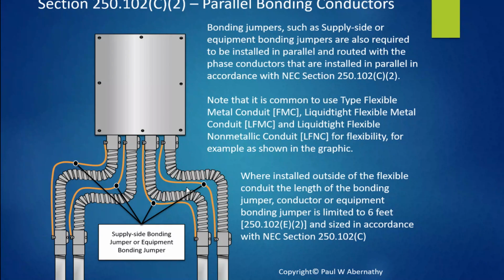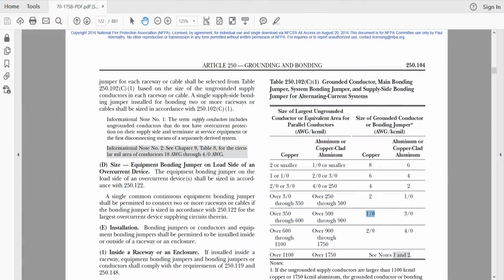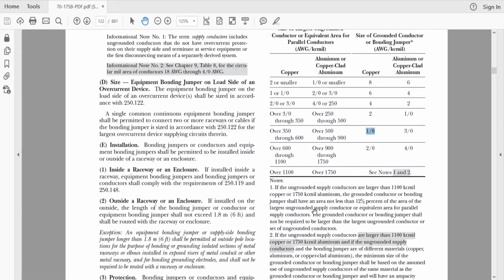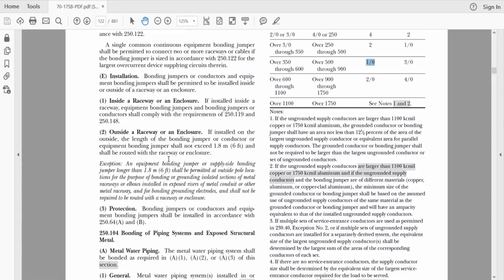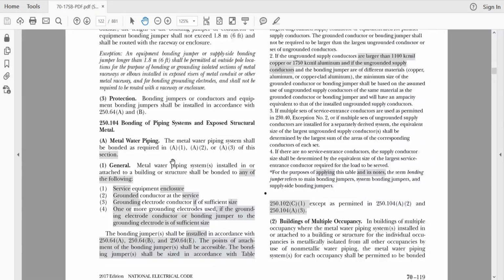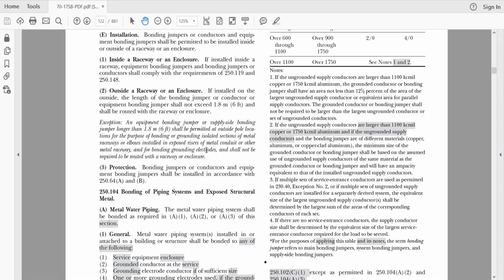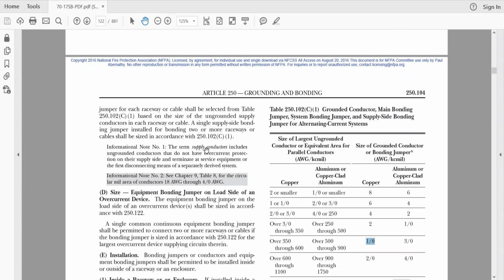If these were service conductors and you're doing this, and this was an acceptable flexible metal conduit type of allowance, then I would have to have this bonding jumper over it. Now, I could have one inside. This is an example shown outside. All right, so now let me go to the code, because I want to show you the actual code verbiage here, and I'll scroll down here. Let me find it here. 250.102C. Okay, right here.